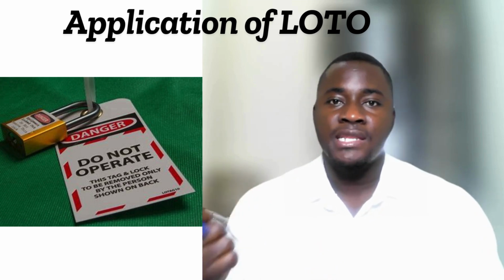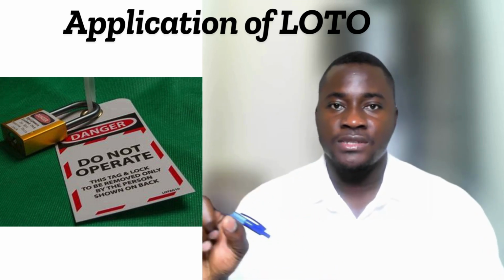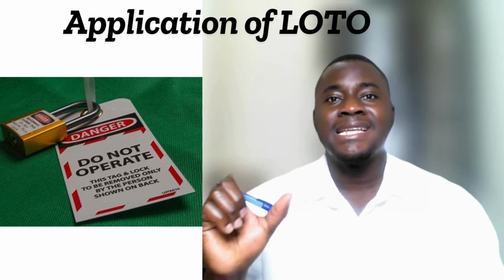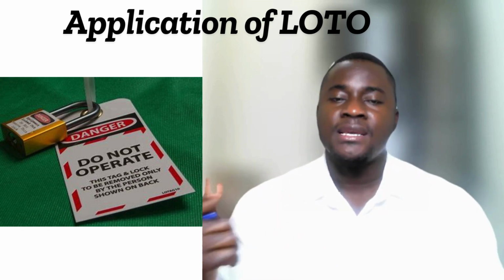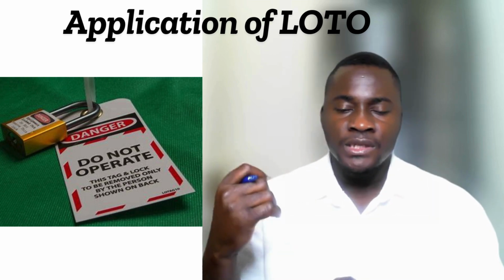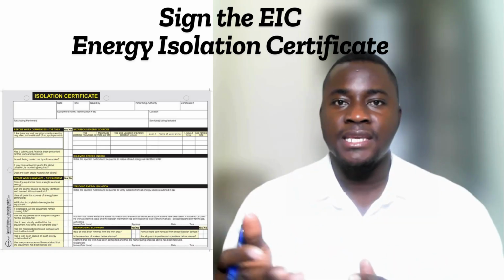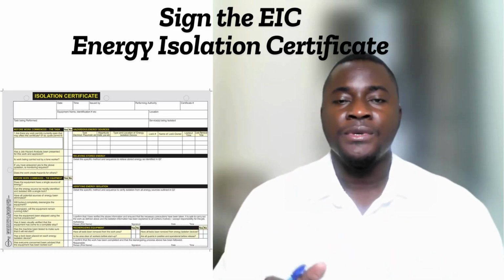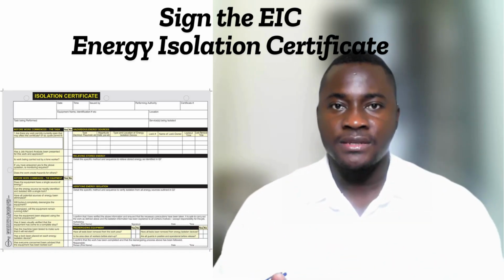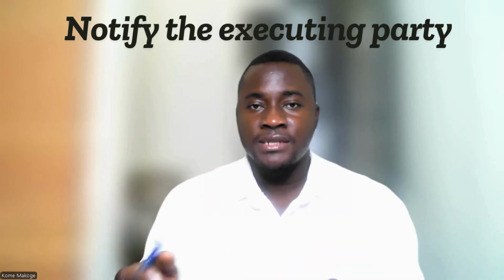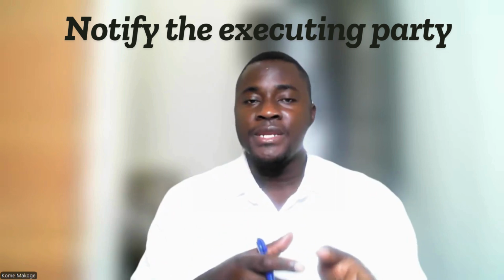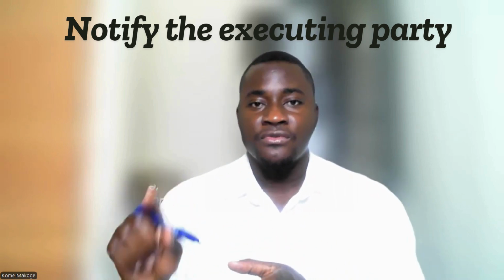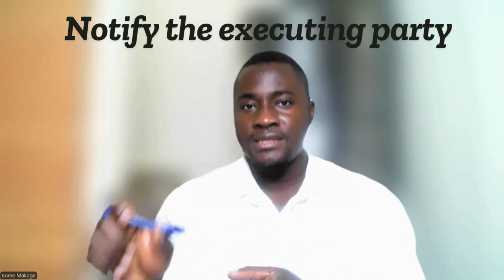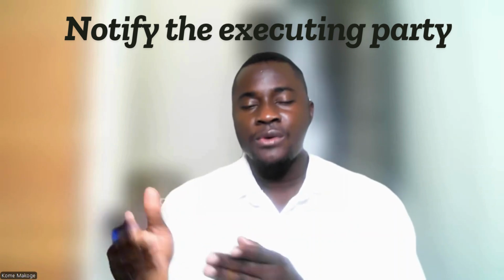Like I said, lockout and tagout is providing a physical lock to a system, as well as putting a tag to it, which stands as an information. Now, once you're done with the lockout and tagout, now you can go ahead signing the EIC or the EICC, which is Energy Isolation Certificate. So once you're done with that, now you notify the executing party saying that you are done with isolation, as well as providing a physical lock, as well as a tag, which is lockout and tagout.